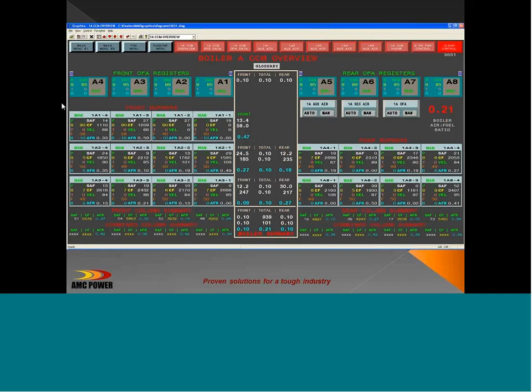I realize some of these screens can look busy. We've got coal flow measurement, we've got velocity of the coal particles, we've got secondary airflow measurement, we've got the airflow register position, we've got air-to-fuel ratios. A lot of people want to have the damper position, the secondary air damper position on this screen. We typically want to put the excess O2 grid on this screen so that an operator can see, if they have a low or high O2, they can look and see, hey, do I happen to have an air-fuel ratio that's not being met?